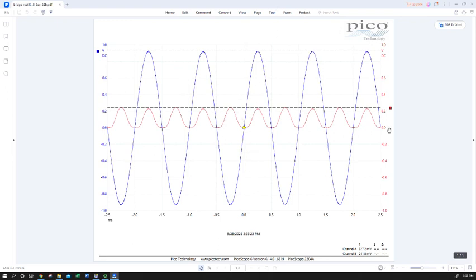But taking a look at this signal, our blue larger amplitude signal is actually the input to the transformer. It is a one-to-one isolation transformer, so N is the same on both sides, so we are presumably getting the same voltage output on the secondary, or at least very close. And the measured value you can see down here, I'm kind of hovering around it in the lower right-hand side of the screen. Channel A is the blue large channel, which is the transformer input.